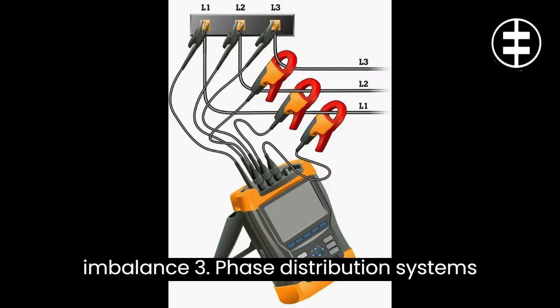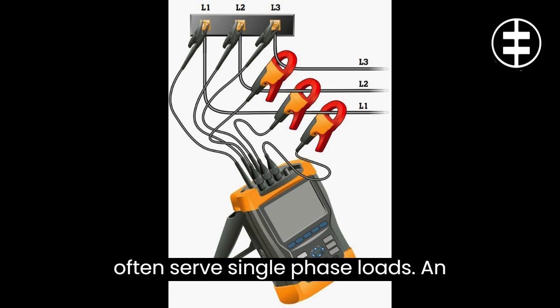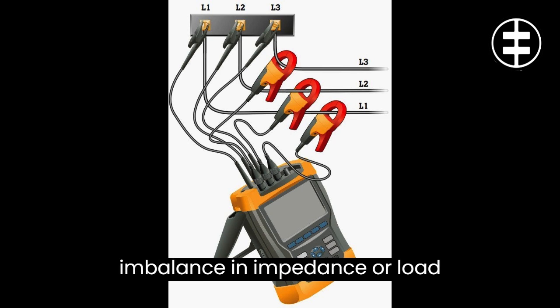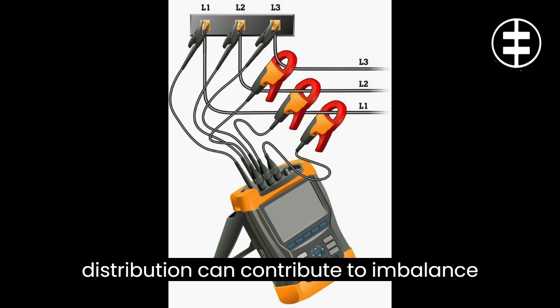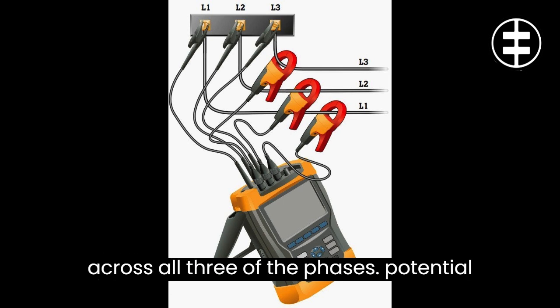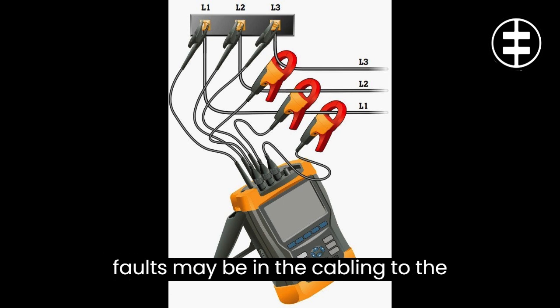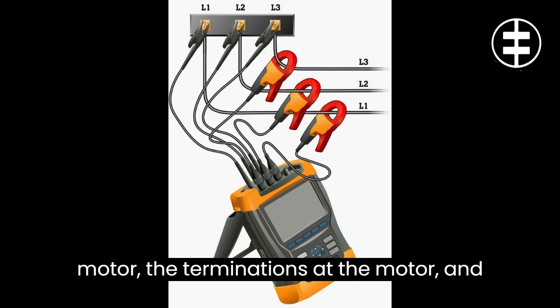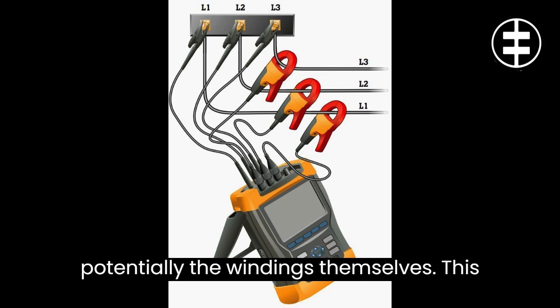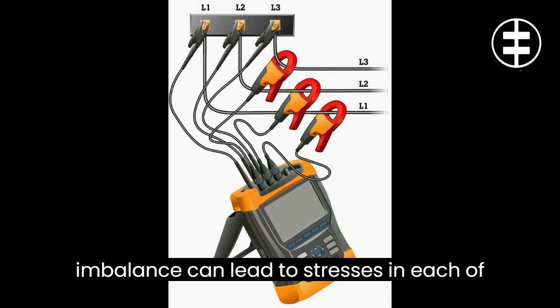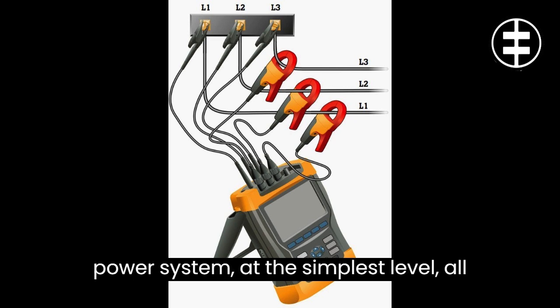2. Voltage imbalance. Three-phase distribution systems often serve single-phase loads. An imbalance in impedance or load distribution can contribute to imbalance across all three of the phases. Potential faults may be in the cabling to the motor, the terminations at the motor, and potentially the windings themselves. This imbalance can lead to stresses in each of the phase circuits in a three-phase power system.